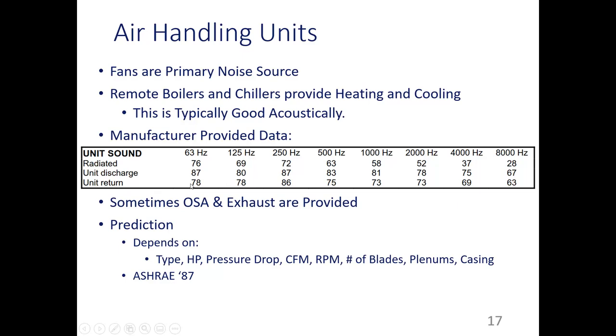I showed you that slide early on in the last lecture where the supply comes in and you have these long ducts that go through the building and spread the sound everywhere. But the return just comes in, and often it's just a grill in the wall. It might come out of the unit, do a 90 degree elbow, and then open to the room. That's something mechanical engineers who don't know any better will try to do in an auditorium. Or in an office setting, they'll just punch down through the roof into that duct right above an acoustical ceiling tile ceiling that provides very little sound isolation. So having the return quieter, since you have this much shorter, much less noise attenuating path, is pretty beneficial.